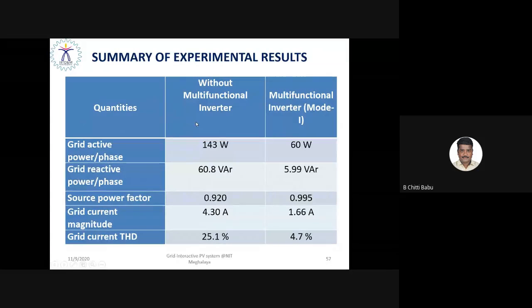Okay, this is the summary of the experimental results, with the multifunction inverter and without the multifunction inverter. You can see the active power demand is reduced from 143 watts to 60 watts. It means 83 watts has been supplied by the solar PV array. Moreover, the grid reactive power support has been reduced from 60.8 VAR to 5.99 VAR. It implies that there is a strong reduction in the reactive power demand by the grid, so the power factor of the grid has been enhanced to unity. The source power factor has been enhanced to 0.995. I mean unity power factor operation, so there is no demand of reactive power, right?